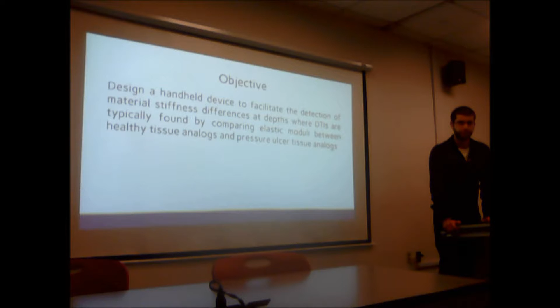By knowing the amount of voltage applied and the distance that the cantilever bar traveled, you're able to detect the elastic modulus. And the way that this works in the iBreast Exam scanner is that it finds a localized region on the patient and is able to detect the elastic moduli of the tissue in that region, and is able to determine what is normal tissue and what is abnormal tissue. And the abnormal tissue can be, in that case, a breast tumor in its early stages. And that device on the market is over 95% accurate in early detection. And so I want to take that technology and its accuracy and create a device to detect the irregular tissue near the bony prominences that would be correlated to a forming deep tissue injury. So the objective is to design a handheld device to facilitate the detection of deep tissue injuries before they require surgical intervention.